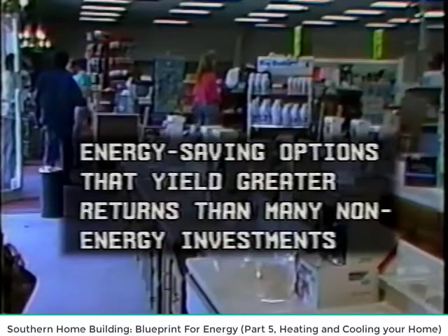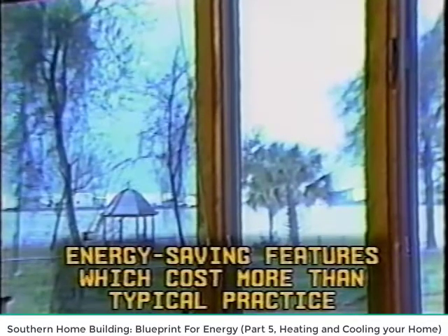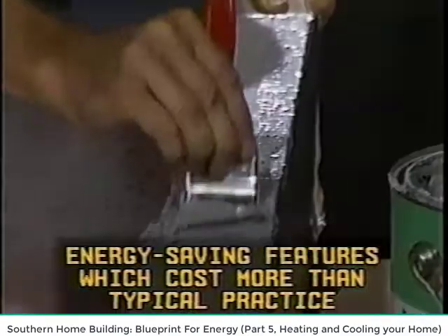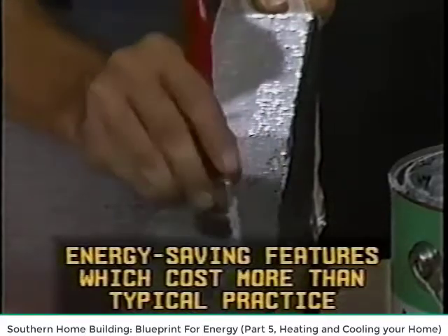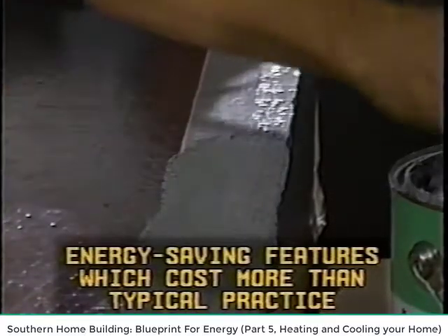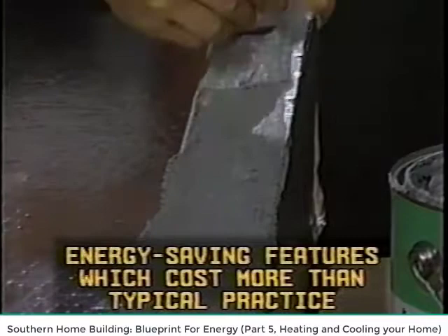The last category of energy-saving options are ones that cost more than the typical practice. So here's a priority list, beginning with the best investments. The top 3 investments are virtually tied, but we'll list them as follows. Number 1, use tinted glass in all windows and doors that are not shaded. Remember to reduce the size of the heat pump when using tinted glass. Number 2, seal the ductwork. Even in many new homes, the ductwork is not as airtight as it should be.